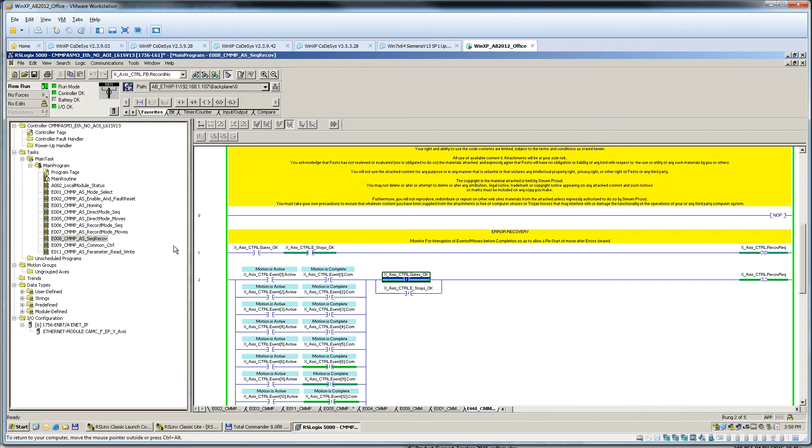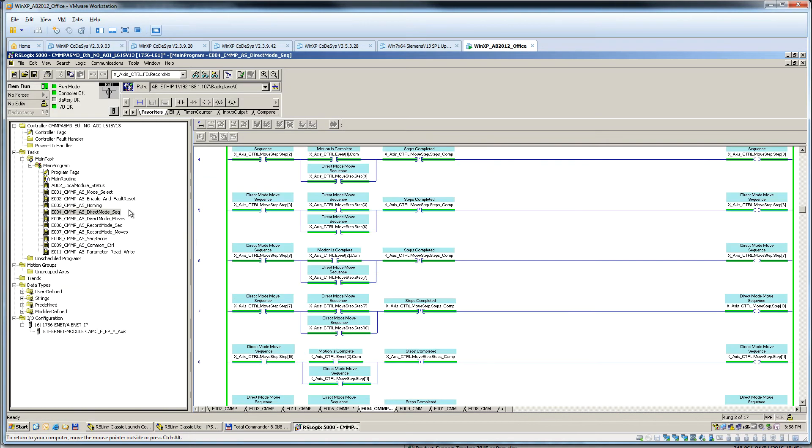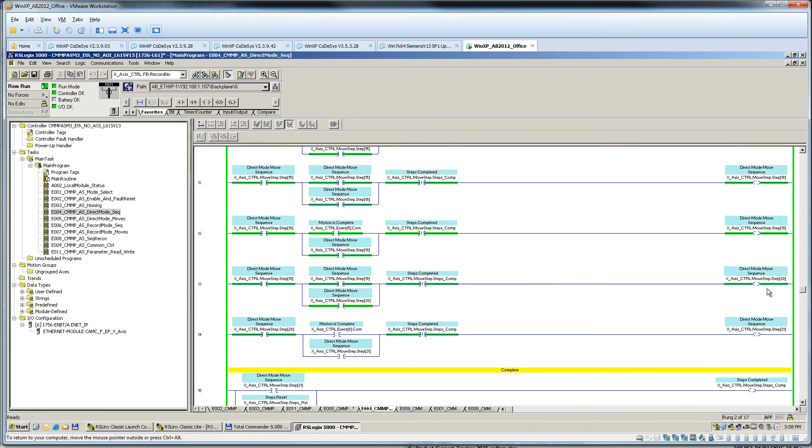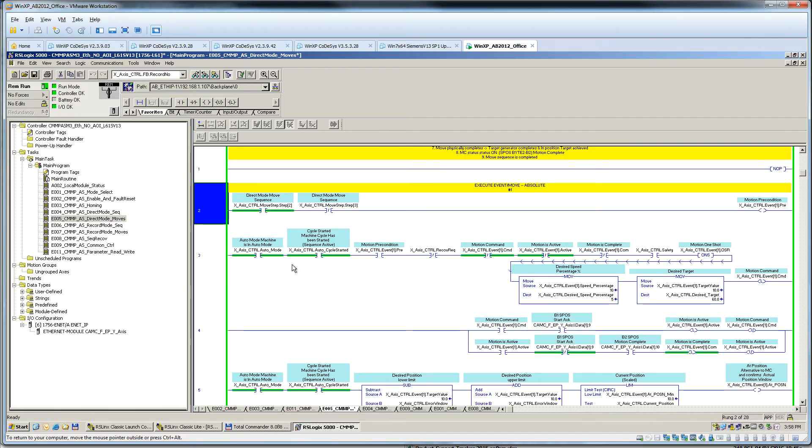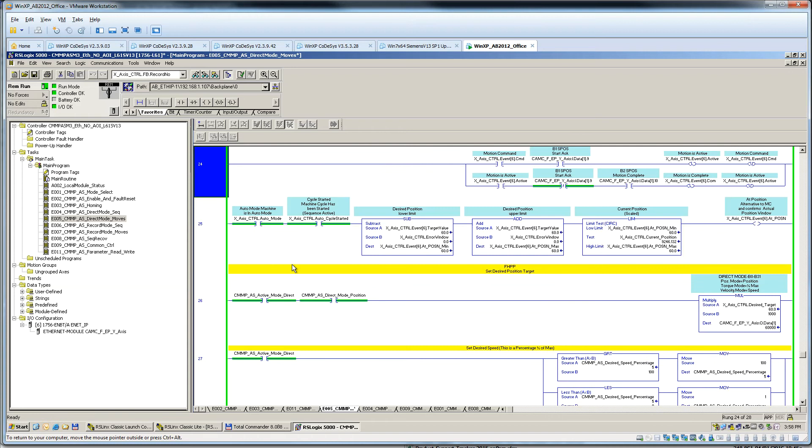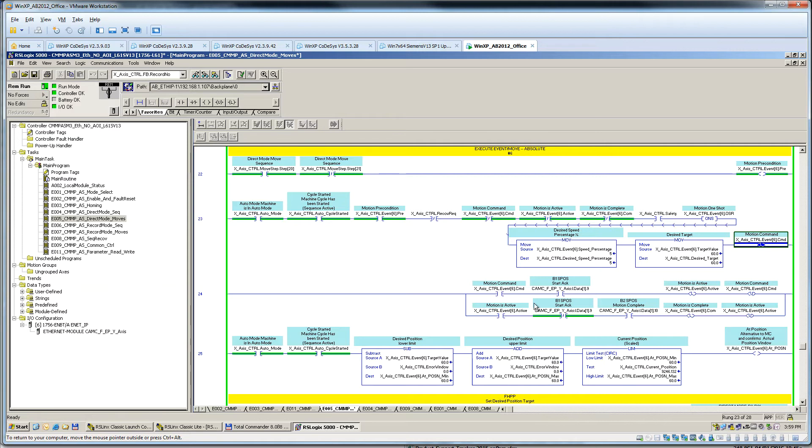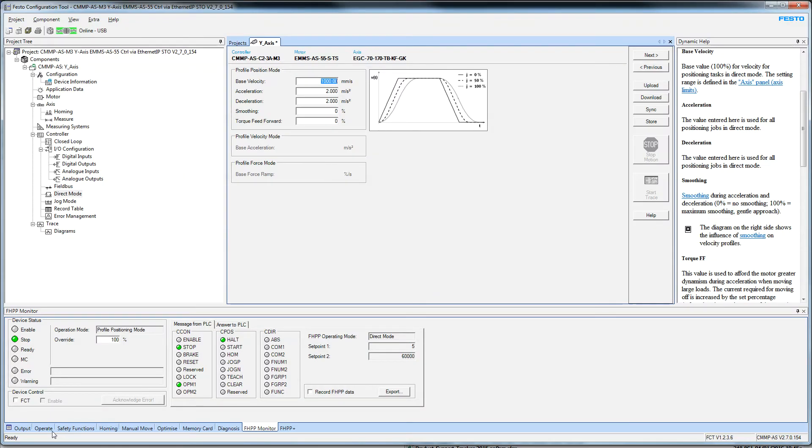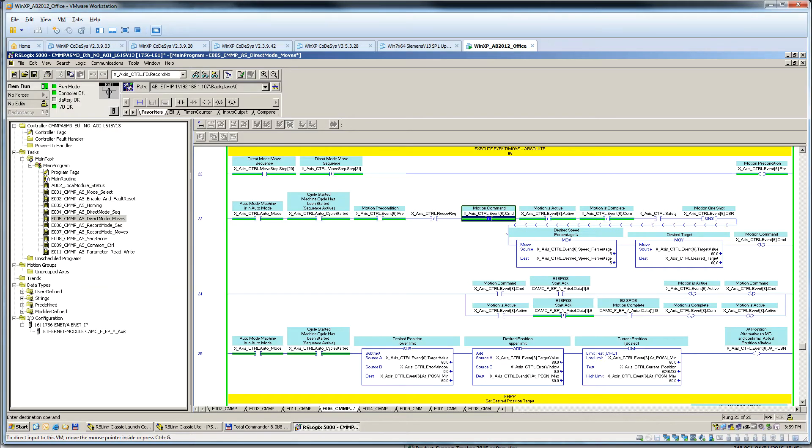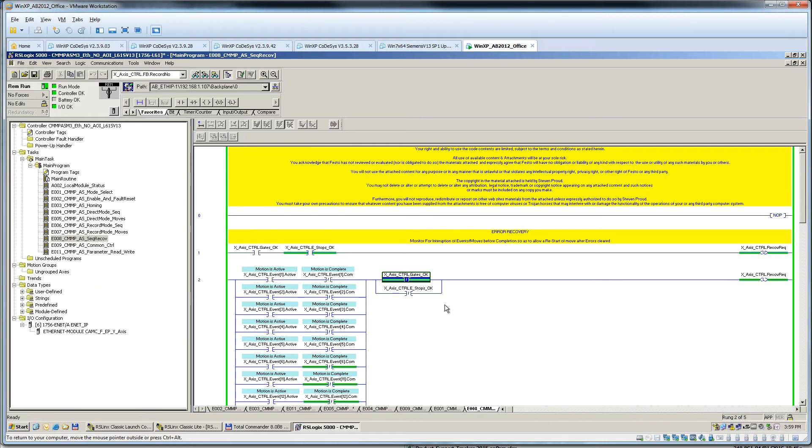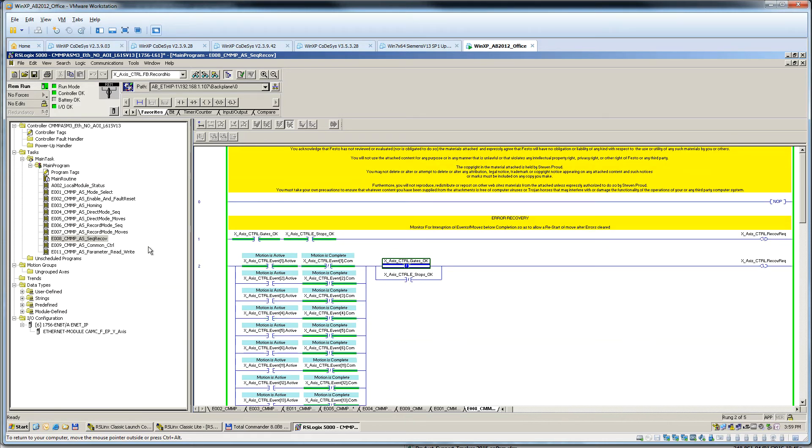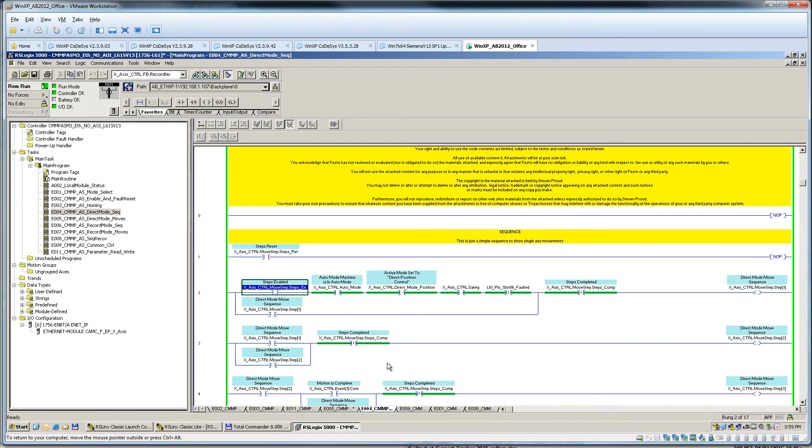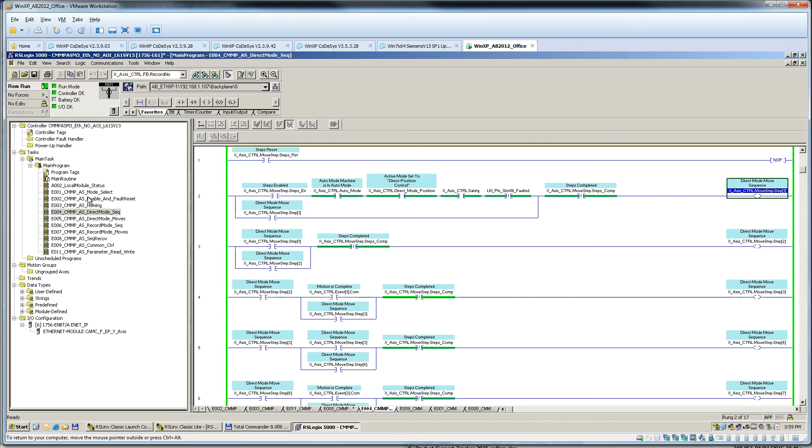Let's say I open the gate. I was just in the middle of doing a move. If I was to follow my code, I am doing step 6. We go to the very end. I had the precondition, I had started, and I was stopped. The target was 60, I'm actually at 54. When I come through and I reset the gate, it immediately takes up and keeps going. You can add some more code to it, but it's basically up and running again. I'm going to turn off the sequencer here. It will finish its sequence of the six moves and then reset itself. The sequence has been reset. I'm going to go change the mode.